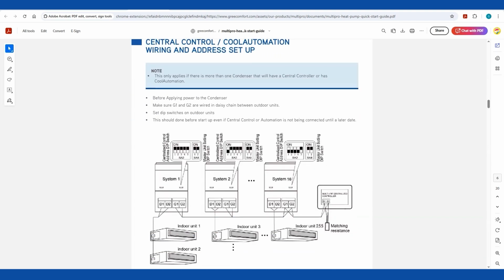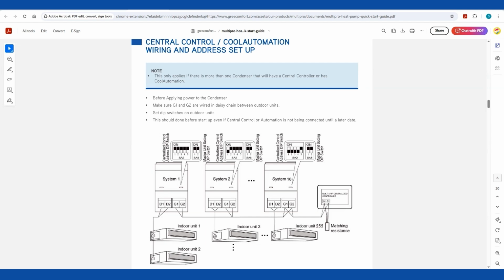One other thing I want to cover with you, just to make sure, before you start up that system and get it all addressed and ready to go, if you're doing this on a small business, or maybe just a large home and you've got multiple condensers and you have the potential for adding either cool automation or central controller, do yourself a favor and preset this unit. Get it all ready to go. Whether they decide to do it or not doesn't matter. So what you want to do is, however many outdoor units you have, hook your wiring up from G1 and G2. So it's just a daisy chain pattern, just like you did before. You had daisy chain from G1 to G2 all across the outdoor units.